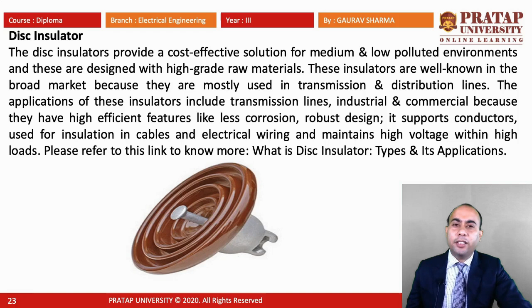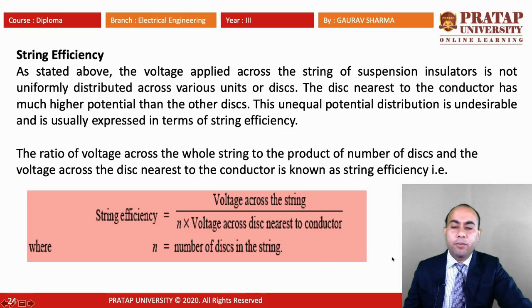Now we go to string efficiency. As stated above, the voltage applied across the string of suspension insulators is not uniformly distributed across the various units or discs. The disc nearest to the conductor has a much higher potential than the other discs. This unequal potential distribution is undesirable and it is usually expressed in terms of string efficiency. The ratio of voltage across the whole string to the product of the number of discs and the voltage across the disc nearest to the conductor is known as string efficiency. So string efficiency is equal to the voltage across the string divided by N times the voltage across the disc near the conductor, where N is the number of discs in the string.